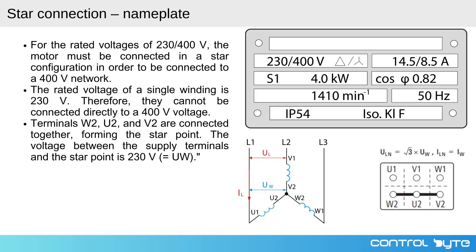The key point here is that the rated voltage of a single winding is 230 volts. Therefore, by connecting the windings in a star configuration, the voltage across each winding remains 230 volts even though the supply voltage is 400 volts.